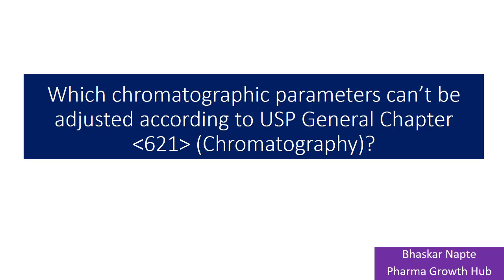General Chapter 621 from the USP deals with chromatography. Adjustment of chromatographic conditions is one of the very important segments of this chapter. According to General Chapter 621, you can make changes into certain chromatographic conditions to achieve system suitability requirements.